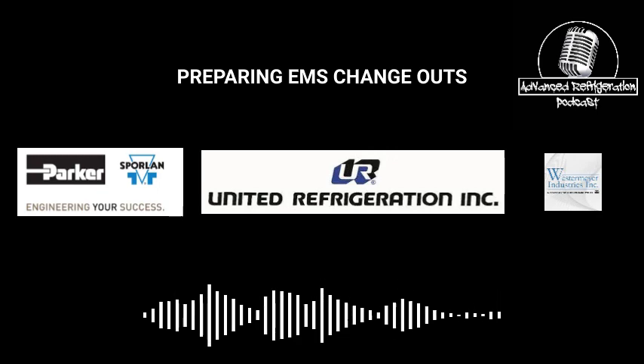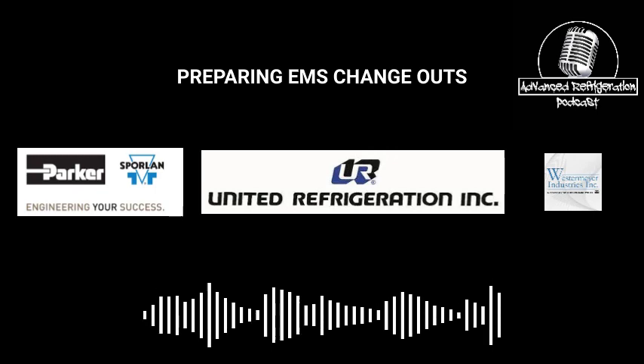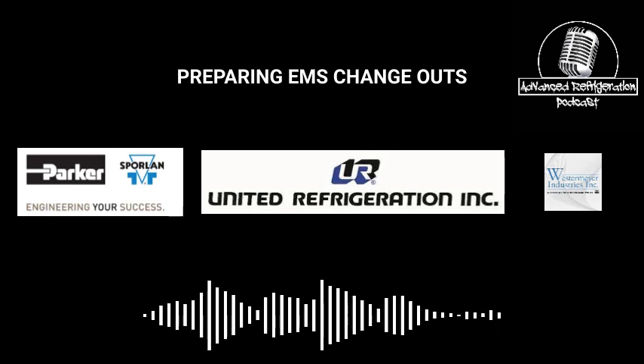I diligently check all of those against each other, make sure we're not cycling on temperature. And if we are, we adjust EPRs. That's not really part of this job, but part of it is making sure everything works properly and is commissioned properly. So you don't want this finger pointing game. Like you don't want the service contractor saying, hey, you did a shit job.